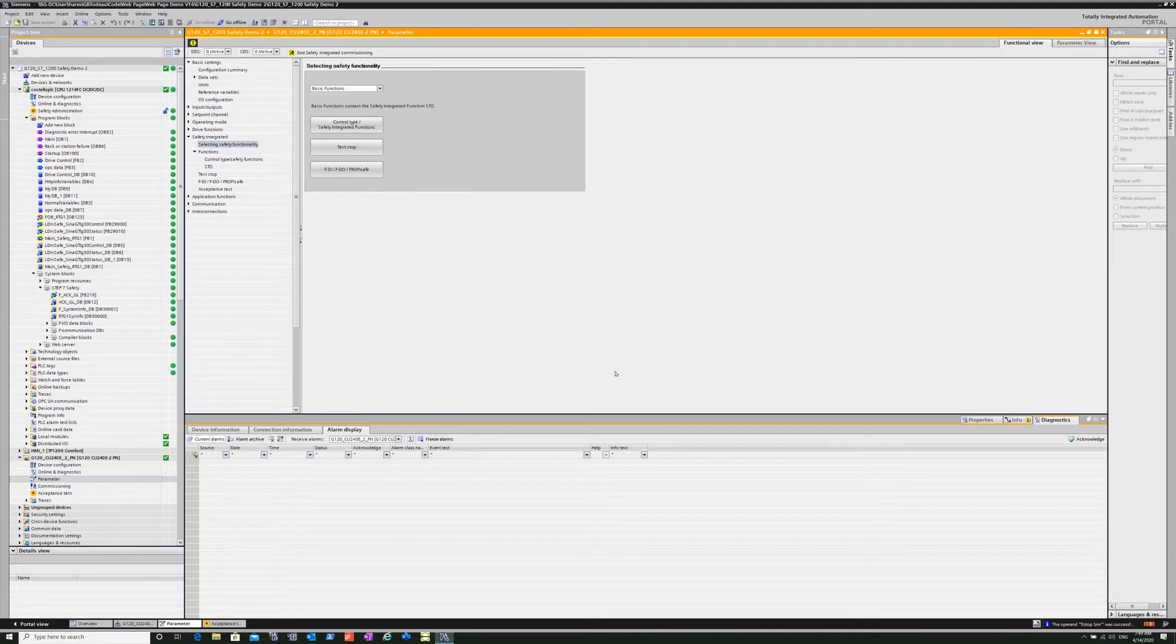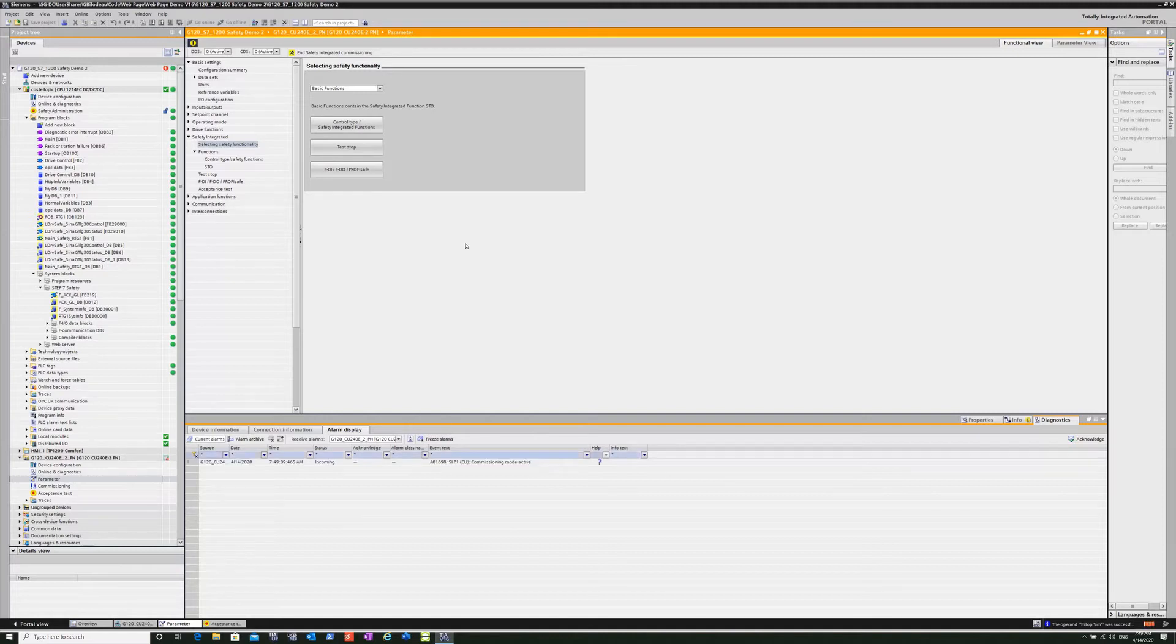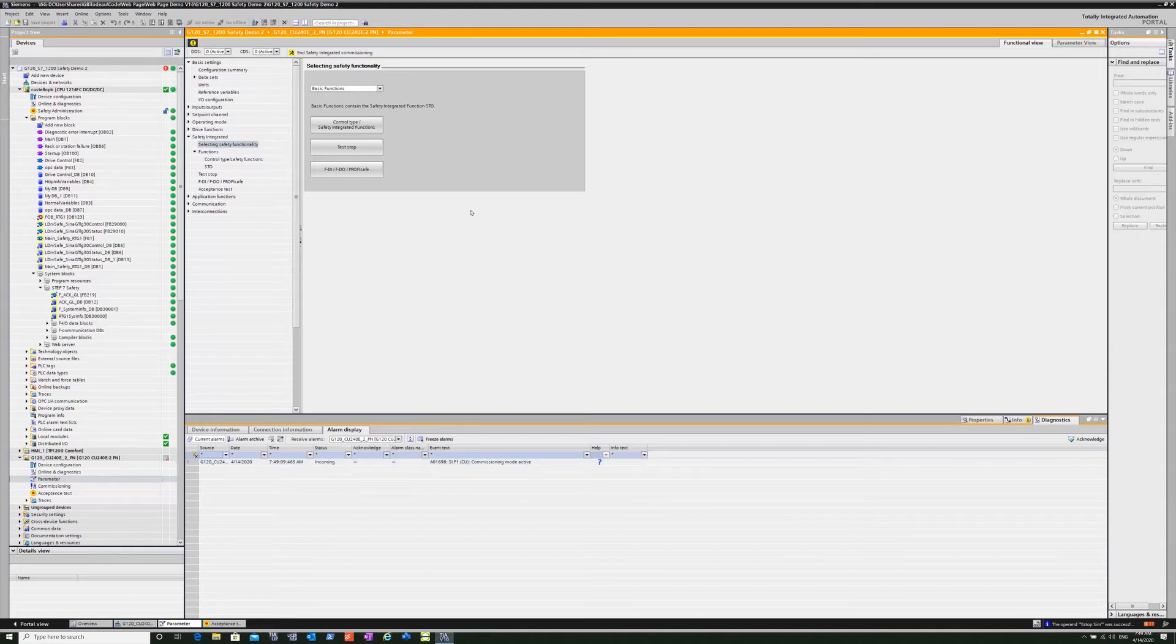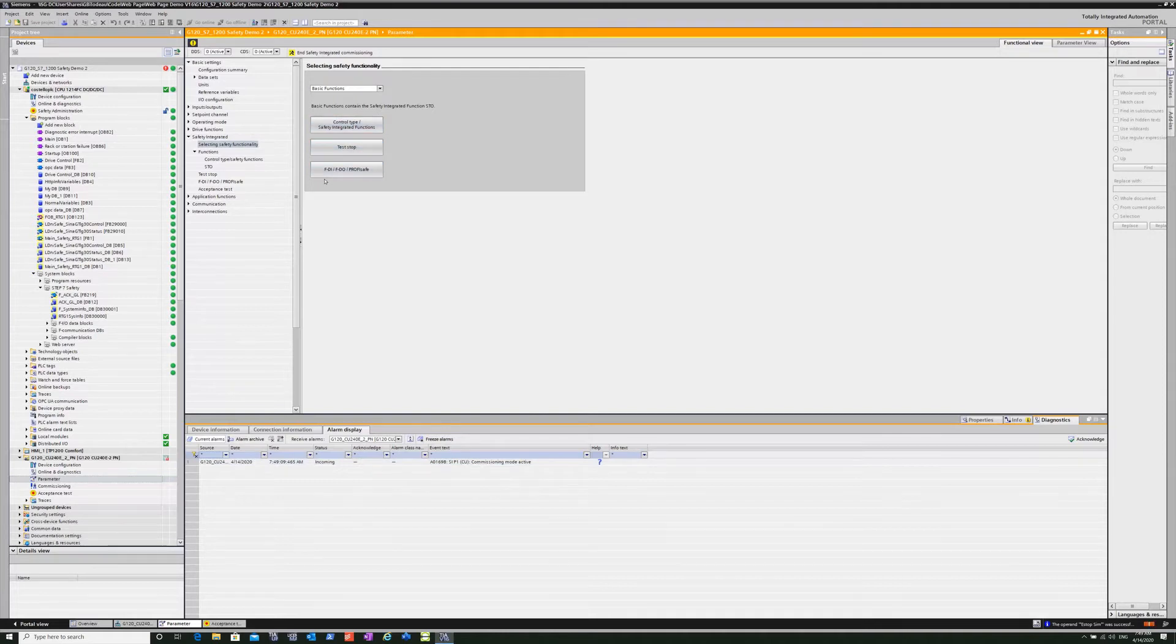So now I'm going to upload the drive itself into the TIA portal project. Make sure everything is synchronized, all the addresses are synchronized, the safety address and everything that needs to be consistent.